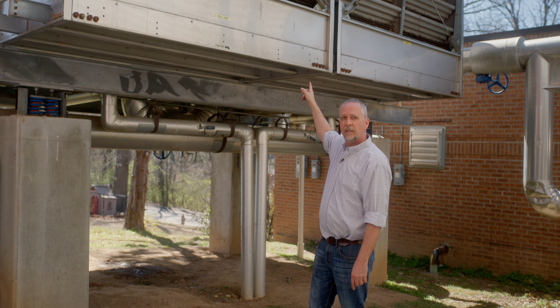In this particular case, these are two separate cooling towers, but I've got two chillers tied on these, and there's a crossover pipe underneath the tower, so I can share both of these cold water basins to make one larger tower, but I may only need to run one fan at a time. So it's a way to save a little energy. We've got enough water capacity here to keep my two chillers cool, but I may not need to run both fans. In mild conditions, I may only need to run one fan.